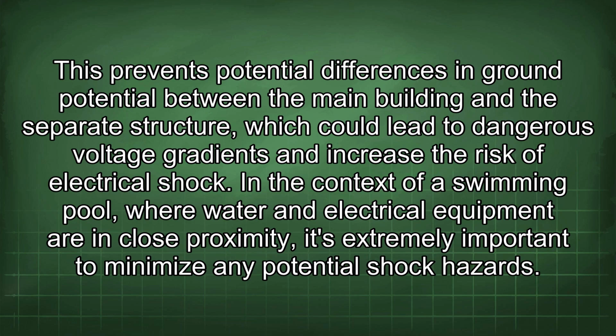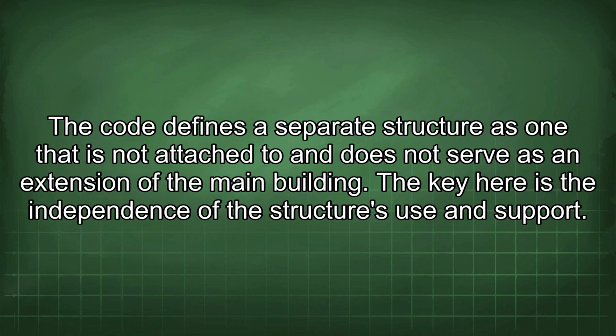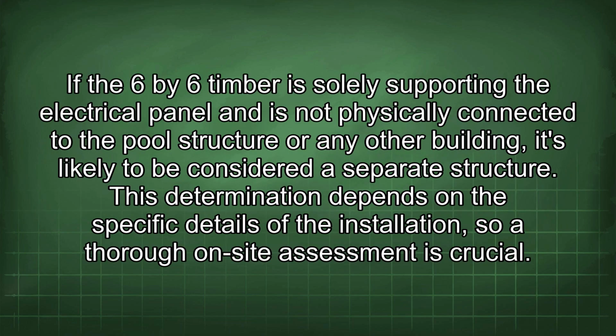In the context of a swimming pool, where water and electrical equipment are in close proximity, it's extremely important to minimize any potential shock hazards. The code defines a separate structure as one that is not attached to and does not serve as an extension of the main building. The key here is the independence of the structure's use and support. If the 6x6 timber is solely supporting the electrical panel and is not physically connected to the pool structure or any other building, it's likely to be considered a separate structure. This determination depends on the specific details of the installation, so a thorough on-site assessment is crucial.